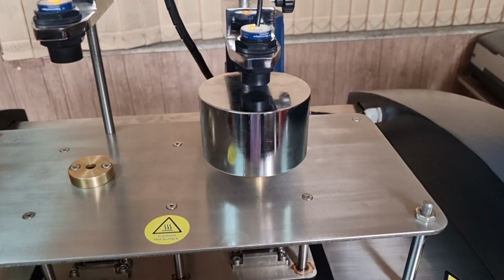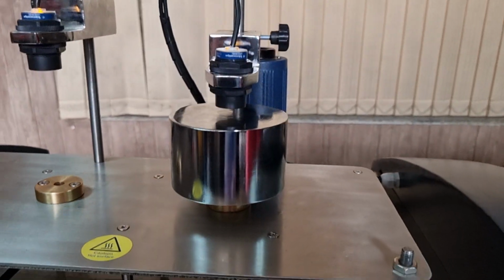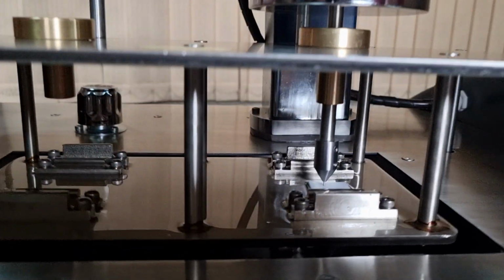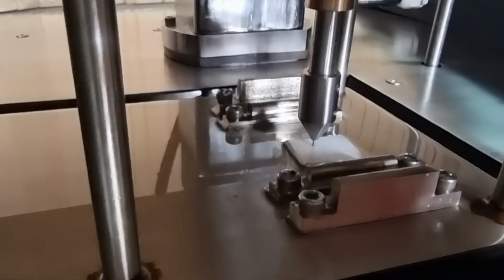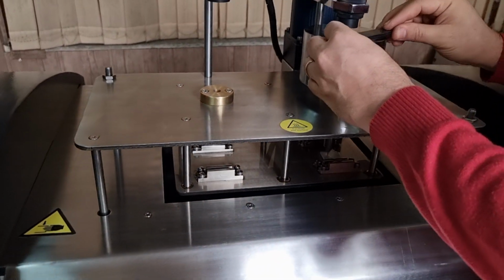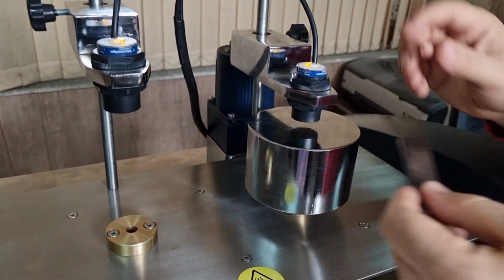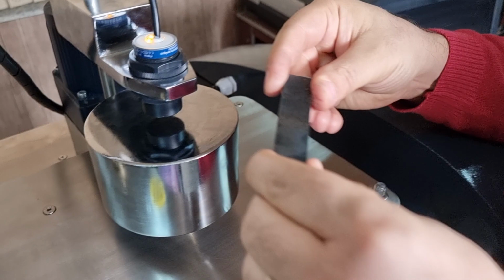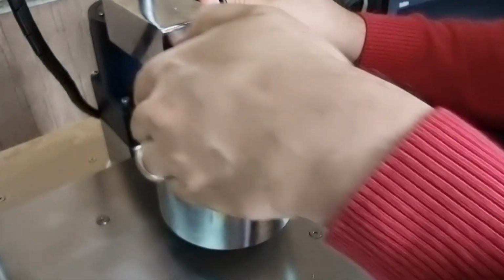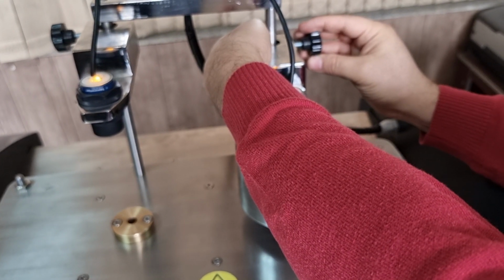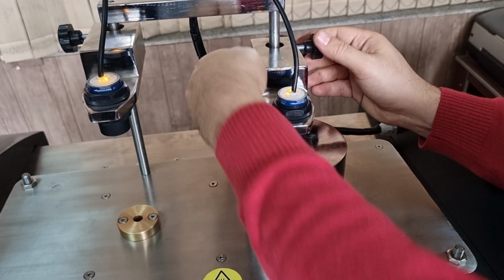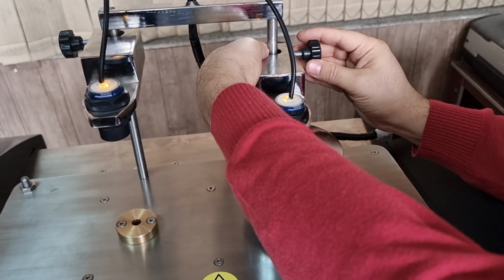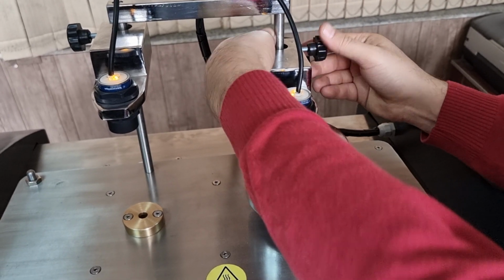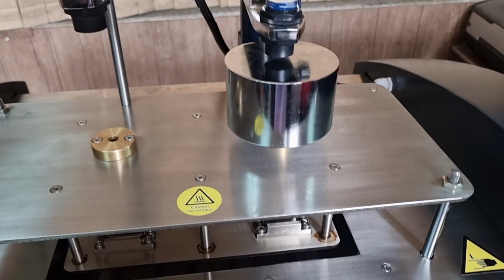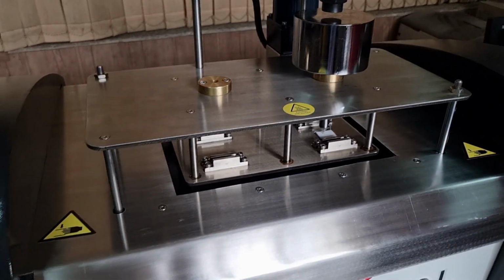After calibration is done for the sensor, you will start the measurement. Now I also put the sample there in the middle of the sample holder. When you're going to start the measurement, you will use the first gauge block that you used for calibration. You will put it just beneath the sensor, move the sensor down, tighten it, and remove the gauge block like this. Remove the gauge block, and this is the start of the measurement point.